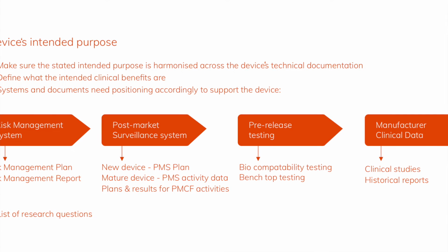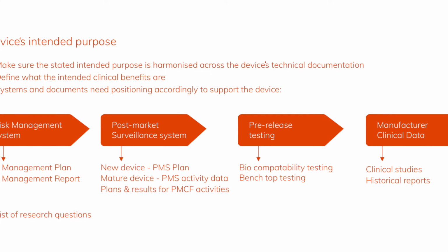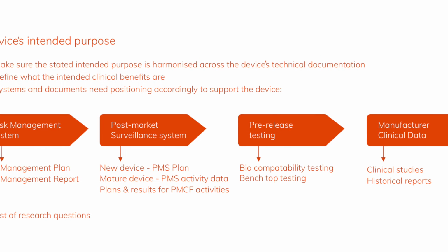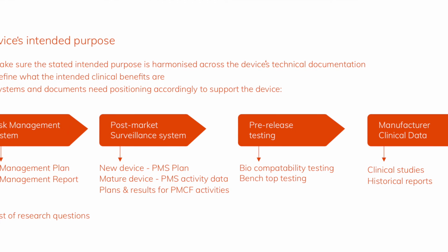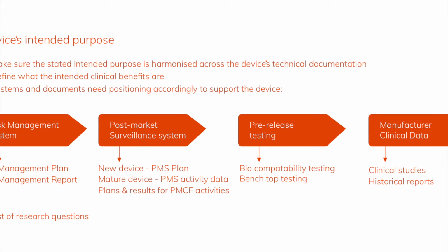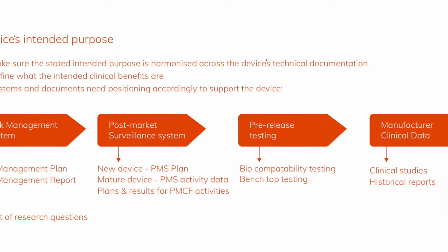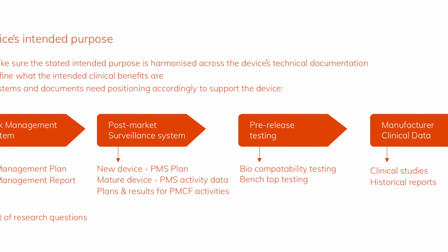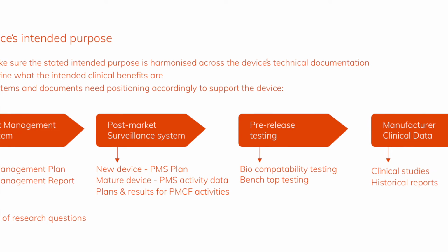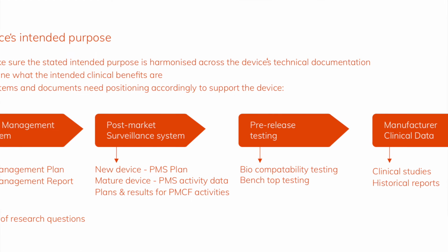It's also necessary to compile all pre-release testing that was performed on the device, such as biocompatibility tests, benchtop tests, and so on. And then also make sure you have access to all manufacturer-generated clinical data. These could include clinical studies initiated by you as a manufacturer or sponsored by you and conducted through investigators with which you are associated. These will all need to be included in the clinical evaluation report. Finally, if there are any historical versions of the clinical evaluation report, along with any comments from notified bodies or reviewers, then these will be invaluable to have at hand when the process of writing the clinical evaluation report begins.